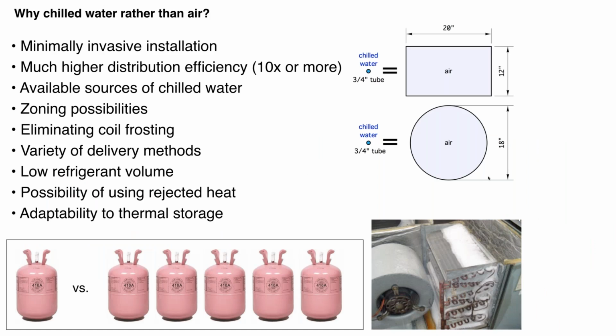So why consider chilled water rather than air side? Well, again, one of the very nice things about hydronics, water can carry almost 3,500 times as much heat per unit of volume compared to air. So the implication is that our conduits, if you will, the material we're going to send our heat transfer material through, water or air, when it's water, it's a much smaller conduit. And you can see here's a comparison based on typical cooling conditions. Chilled water in a 3/4 inch nominal tube size has the equivalent cooling carrying ability of a 12 by 20 inch duct or an 18 inch diameter duct. And obviously it's going to be a lot easier to integrate that tube into a structure with minimal disruption of structure, minimal aesthetic compromises and so forth.